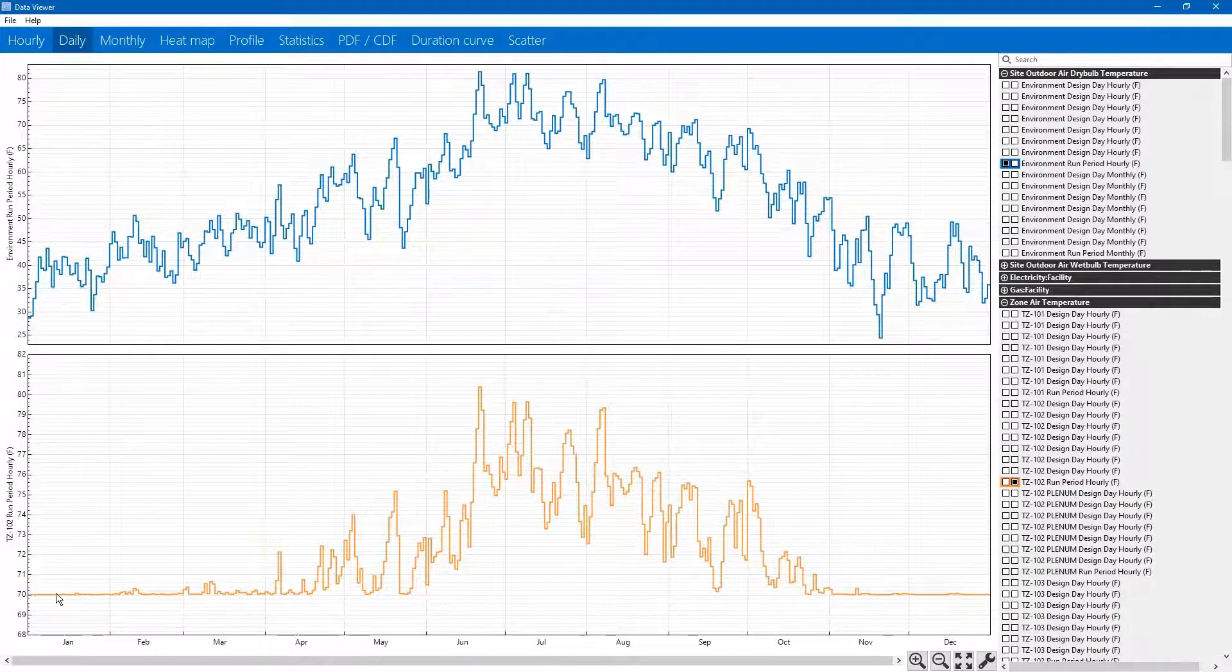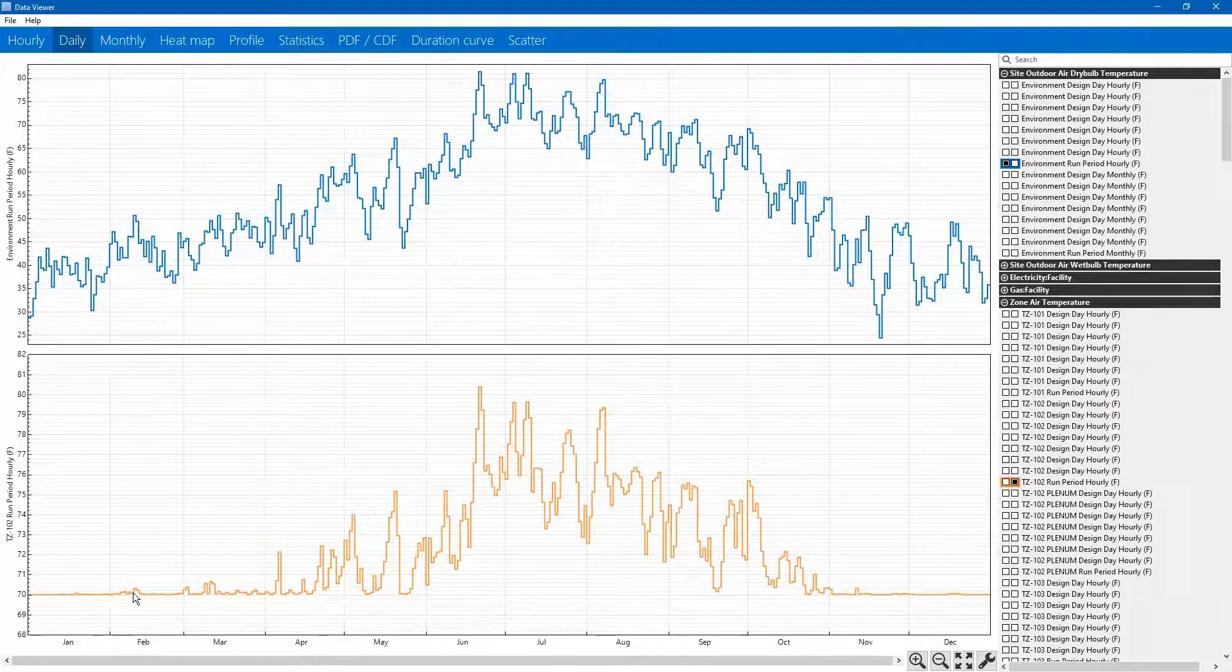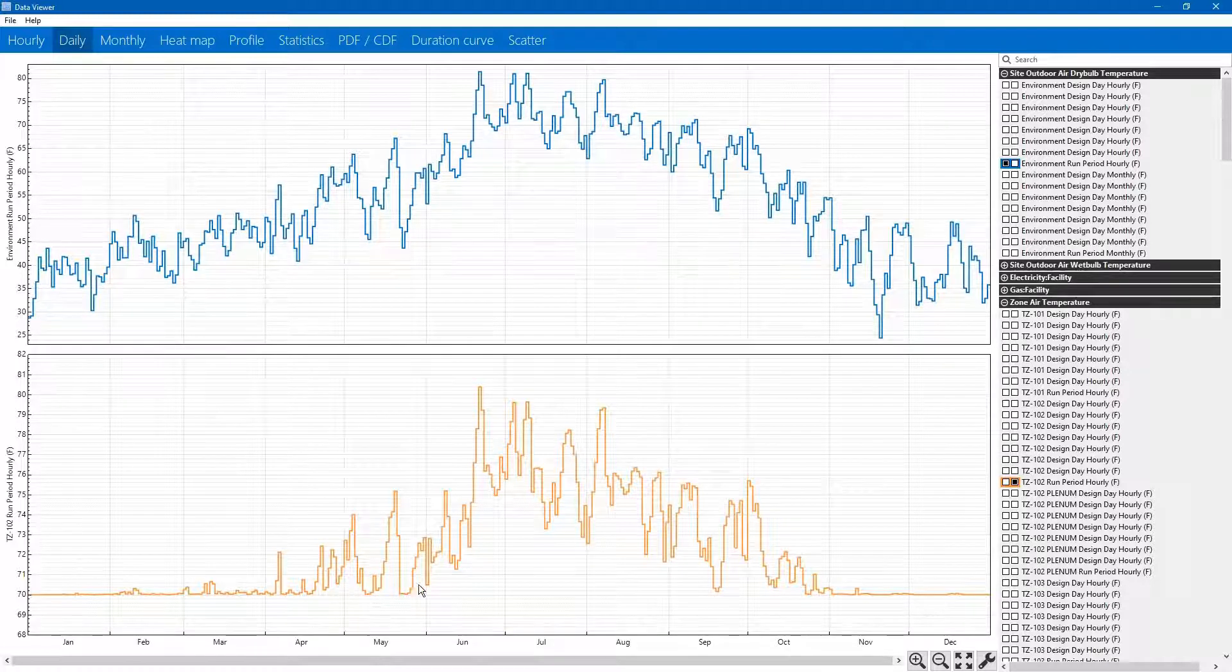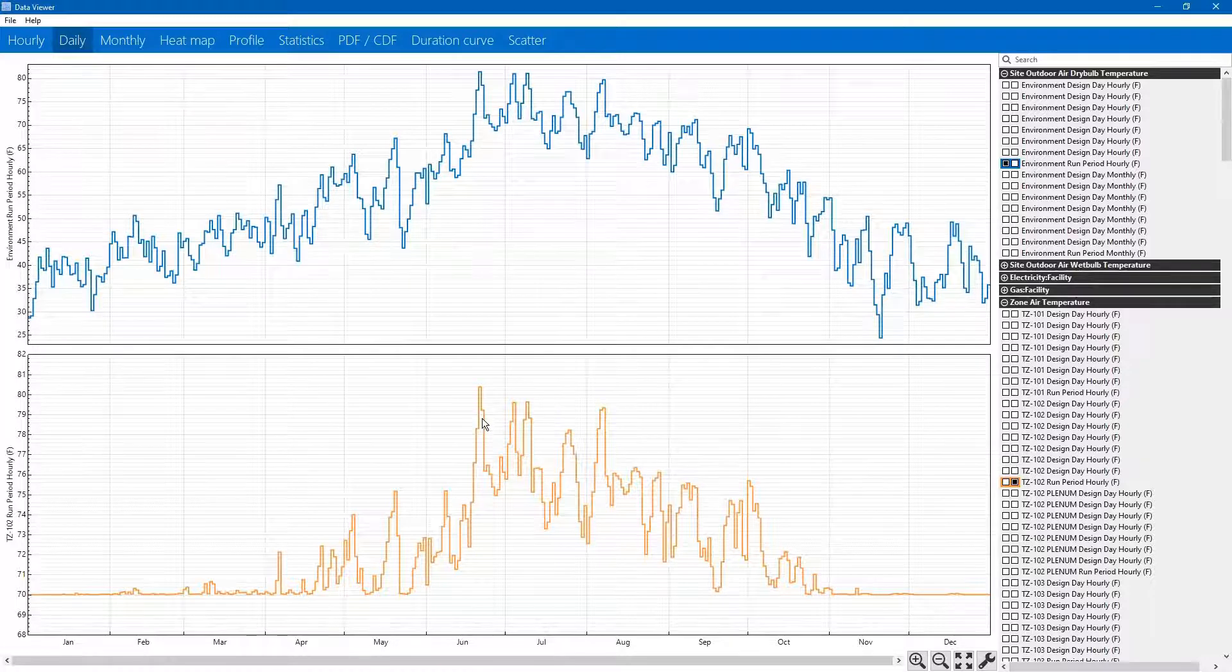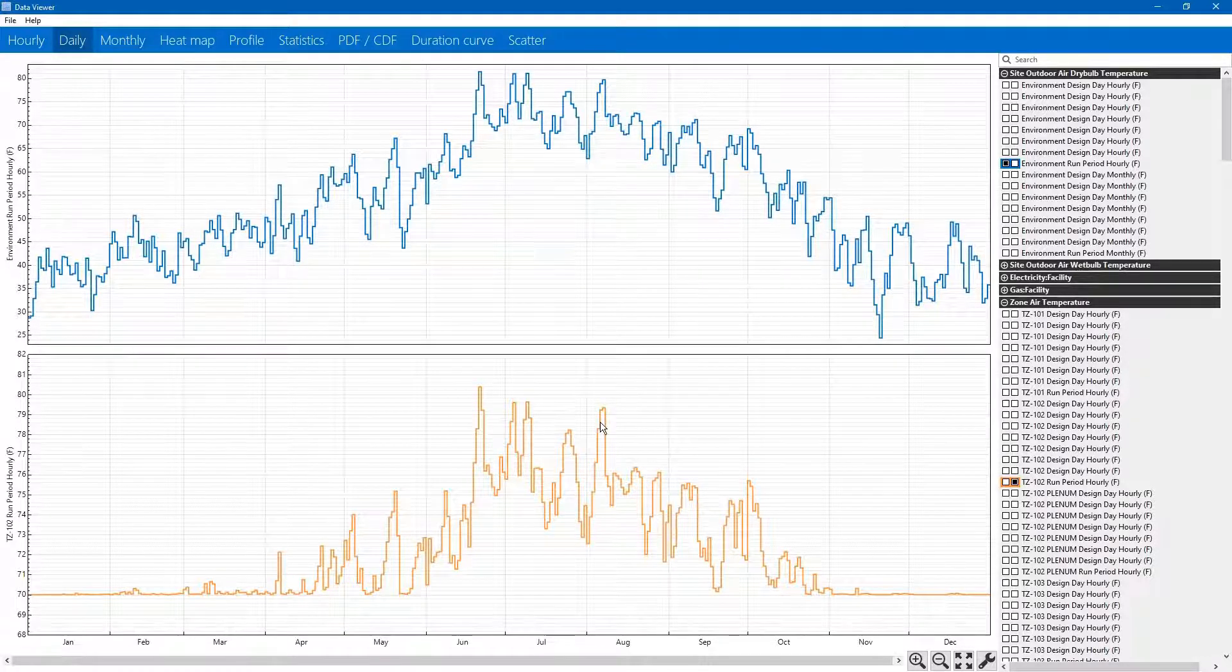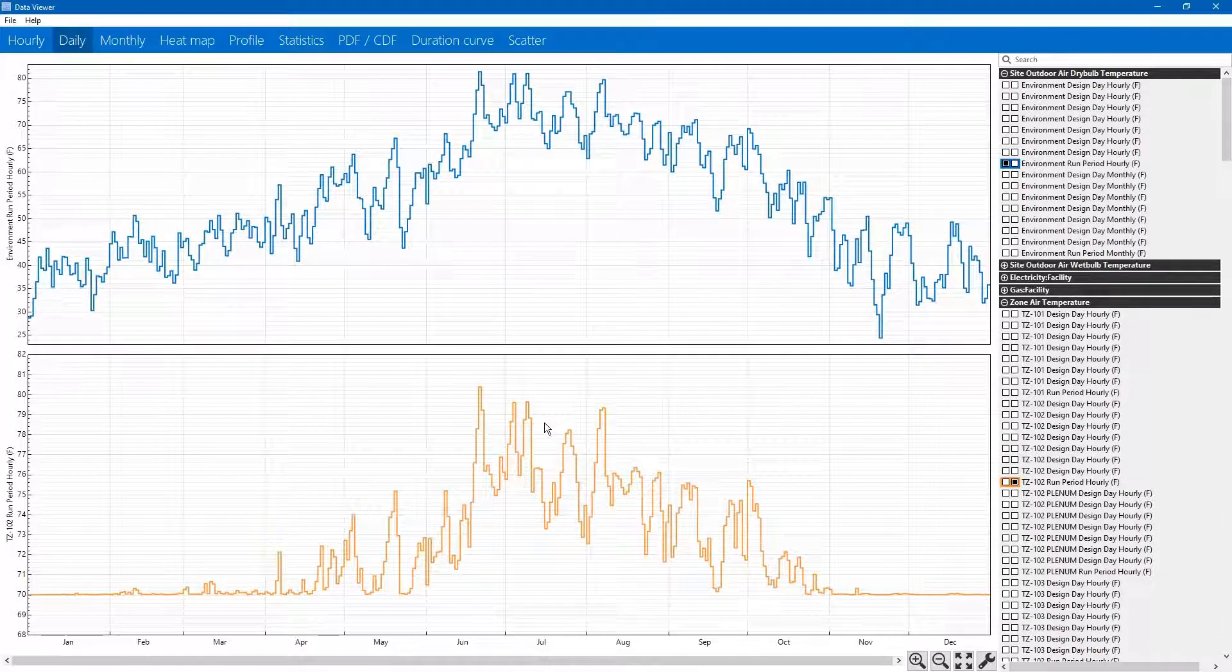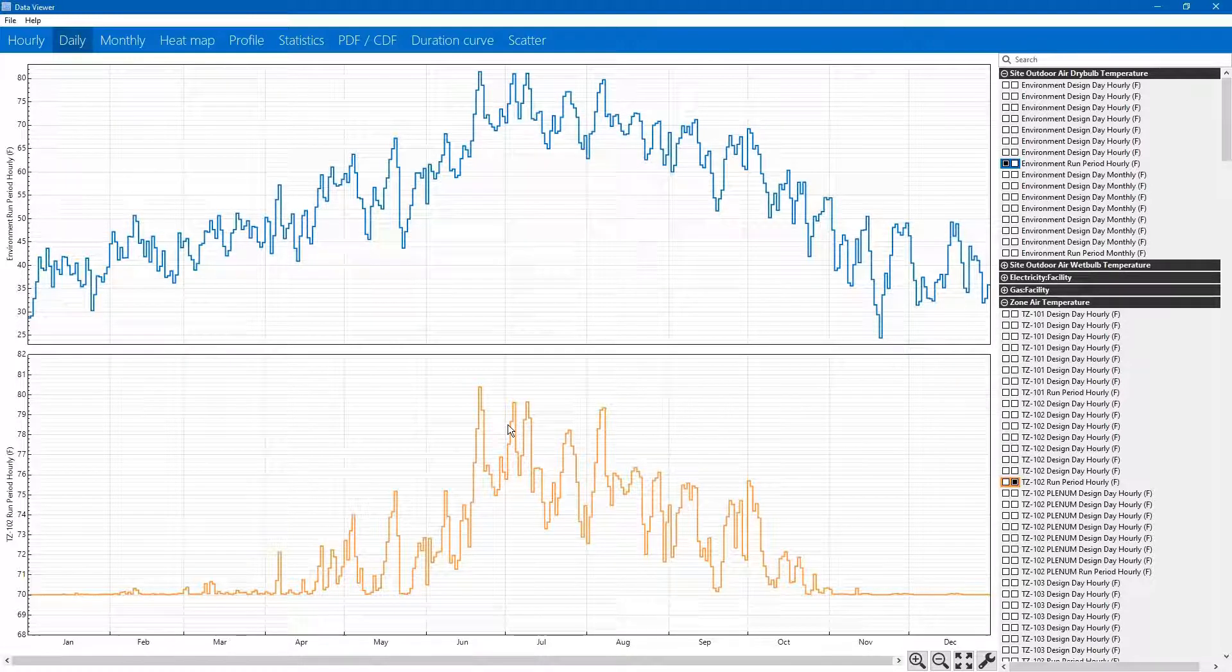During the wintertime, you can see that the space temperature maintains a pretty steady 70 degrees now. We are not having those overheating problems. The temperatures do climb during the summertime, but that is to be expected, especially in a laundry room where we do not have any active cooling systems maintaining those temperatures. It looks pretty reasonable.